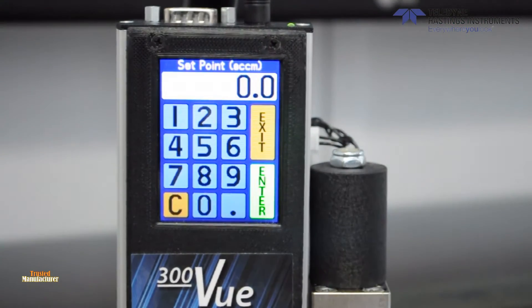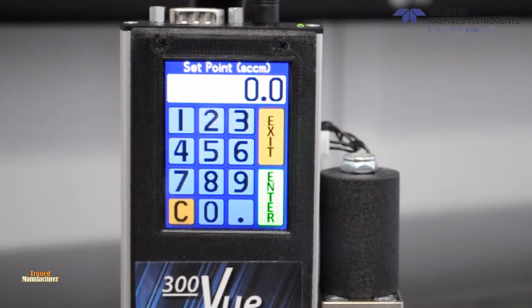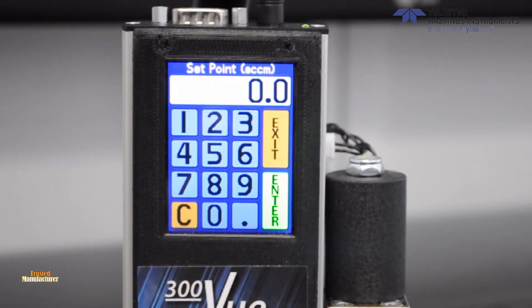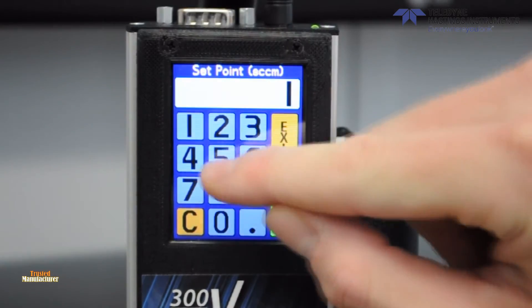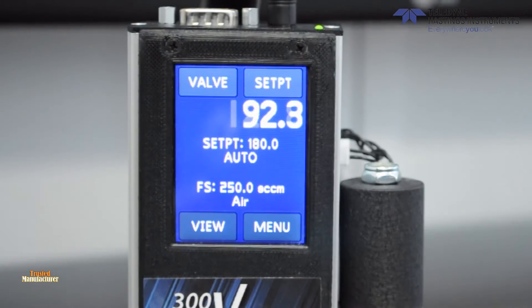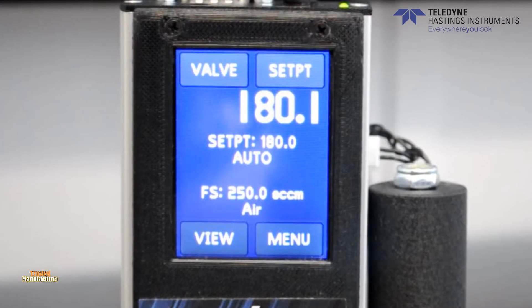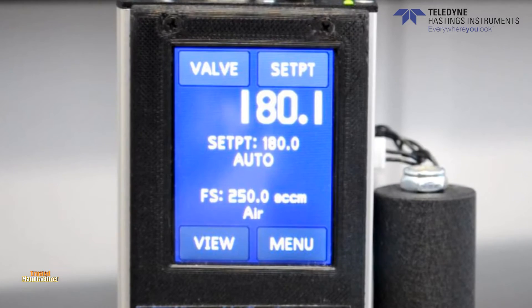The 300 Vue will allow you to manually select the set point desired. By clicking the top right menu, you are brought to a numeric keypad. Depending on the internal settings of the instrument, the set point can be entered as a percent of full scale or as a flow value in display units. The valve button in the upper left-hand corner allows you to override the set point to fully open or purge, or fully close the valve.